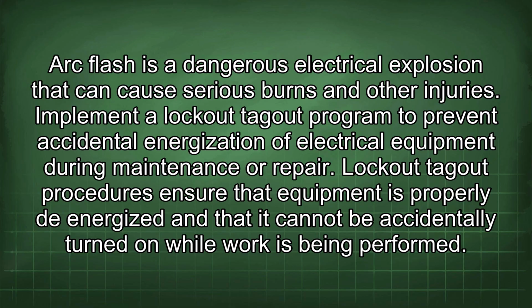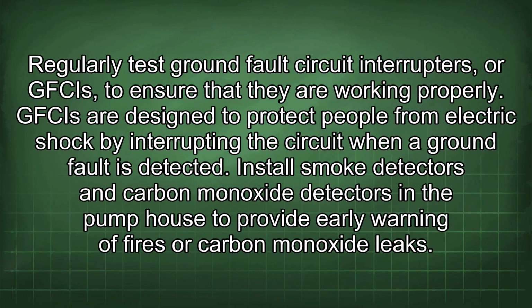Implement a lockout-tagout program to prevent accidental energization of electrical equipment during maintenance or repair. Lockout-tagout procedures ensure that the equipment is properly de-energized and that it cannot be accidentally turned on while work is being performed. Regularly test ground fault circuit interrupters, or GFCIs, to ensure that they are working properly. GFCIs are designed to protect people from electric shock by interrupting the circuit when a ground fault is detected.